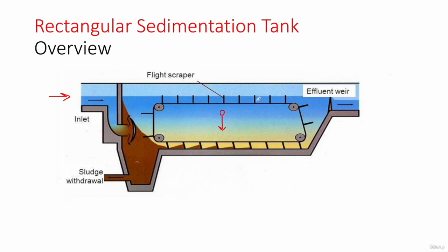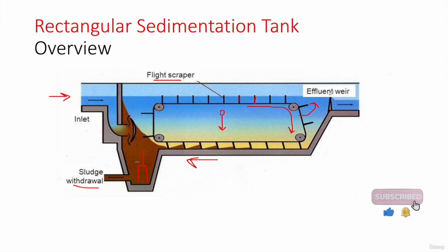These particles form a sludge layer. To remove this layer, we have a mechanical device equipped with flight scrapers. This device rotates and the scrapers move the sludge into a hopper. From the hopper, the sludge is withdrawn by gravity if possible, or pumped for further treatment to be safely disposed of or reused. The clean water then leaves through an effluent structure to minimize turbulence.